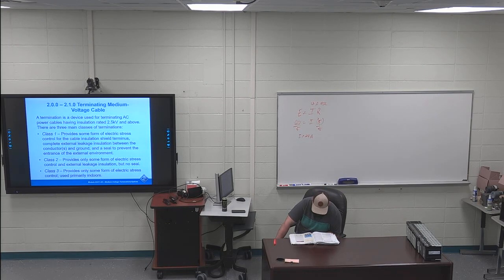Grounding. I don't have anything in grounding the shield's ends, but for my instrumentation students, this is where it's different. First sentence of 212 says that all shields are normally grounded. However, individual circumstances may exist where the shield ground is only at one end. It's called floating one end, like we do in instrumentation. These are power cables. They are not signals. They're not sending signals across these cables. So they are not the same as an instrumentation cable for all y'all out there. They're different. So most of the time you are grounding the shields on both ends.